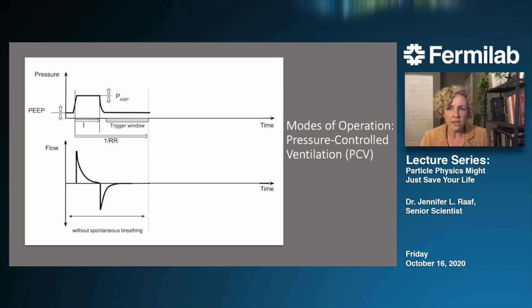So you can see in these charts that the pressure is kept constant during the inhalation. That's the flat top of the upper graph. And the flow slows down over the course of the inhalation as the lungs fill. At the end of the inhale, the applied pressure is removed by closing a valve in the ventilator, and then you see that the direction of the flow reverses, and the pressure falls back down to its baseline level, or PEEP.